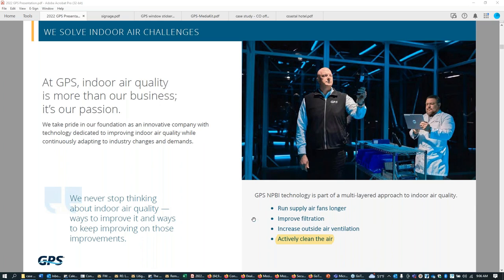Second guidance they said was improve your filtration. If your buildings are capable of tolerating MERV 13 filters, upgrade from 8 or 10, whatever you have, to MERV 13. Not all buildings could do that. They're not all designed to run with that pressure drop. But I think, at least with my peers and colleagues before I left the real estate industry, everyone seemed to be gravitating toward that MERV 13 as a standard, at least in the Class A properties.